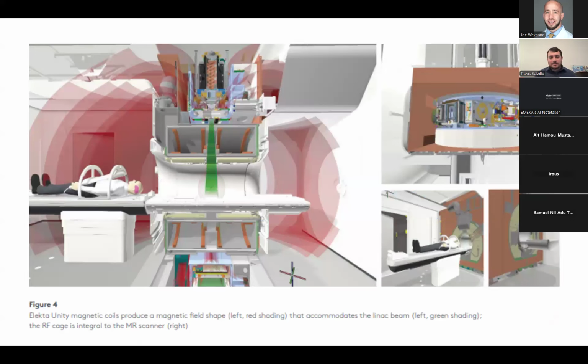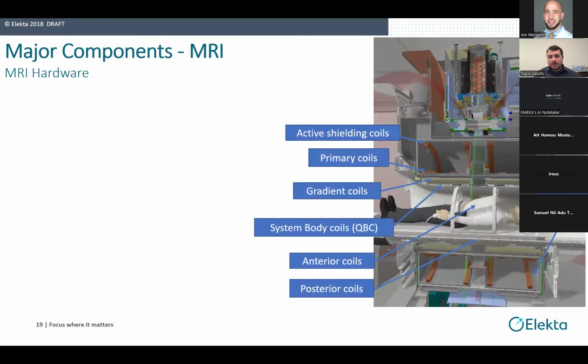This is just a schematic of what it would look like. It's, again, very similar to what you saw with the Versa HD linear accelerator system. Again, you have your shielding coils, your primary coils, everything you would expect in an MRI you have on your linear accelerator. The one thing you also have to worry about is a cryostat that does limit your field angles. You have a very, very small area that you tell the beam not to treat through because you don't want to be treating through the cryostat.